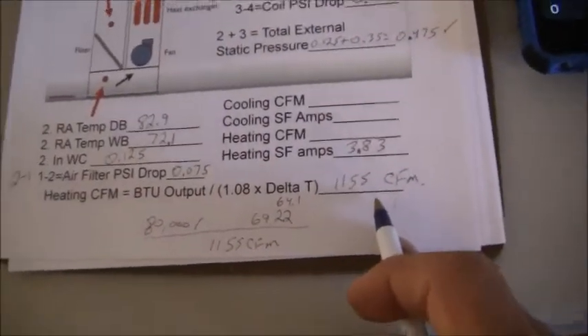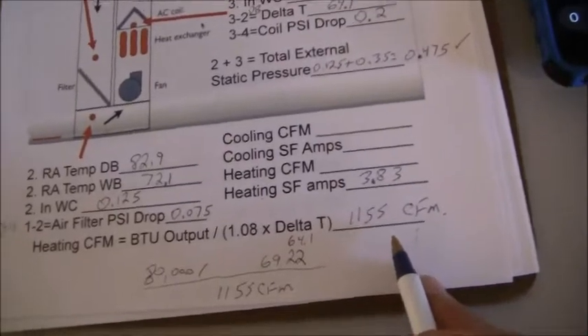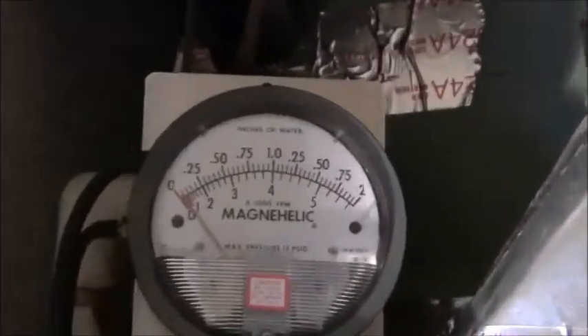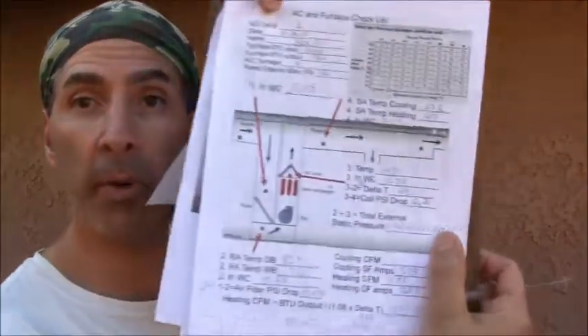We'll compare that up against the cooling CFM and see what that is once we get into the cooling. Okay, the furnace is shut off. We're at 95 degrees Fahrenheit on the thermometer right there, so the fan has shut off. You can see the magnehelic gauge is turned to 0 because the supply fan is shut off. Okay, that concludes the video. So you saw the checklists. I had 2 checklists. This one here was pretty much for the AC, and the other checklist, which is this one here, is pretty much for the furnace.